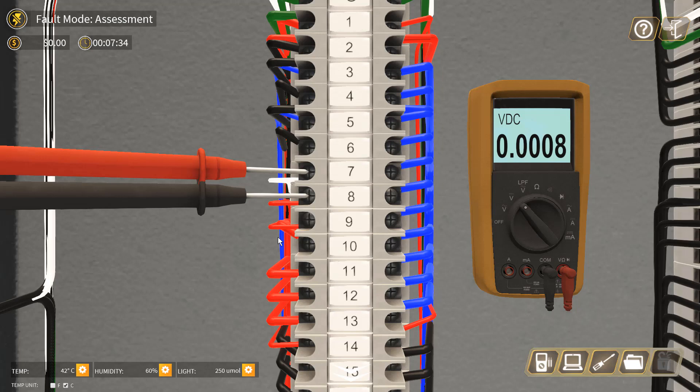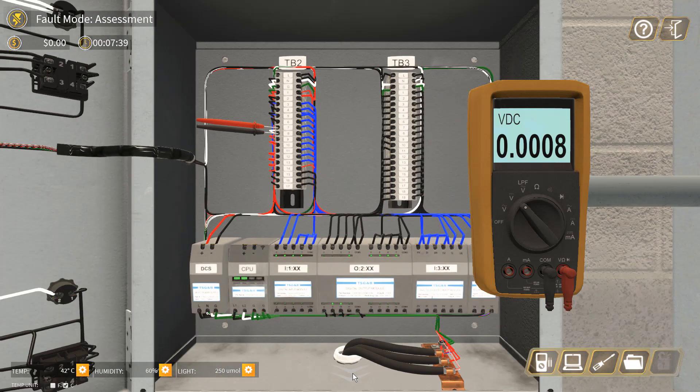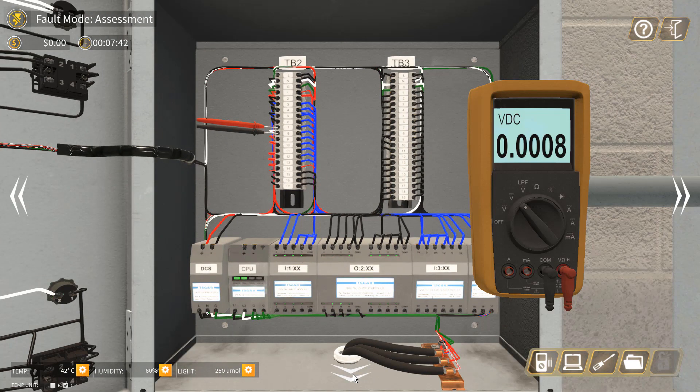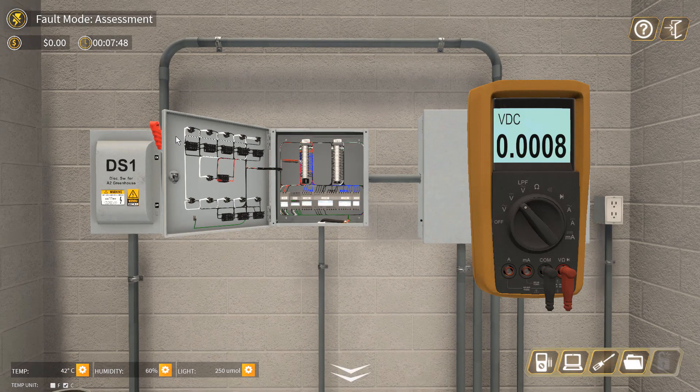To check the RTD, we need to measure the resistance, but the resistance cannot be measured live. So we have to shut down the power supply and perform the local lockout/tagout.